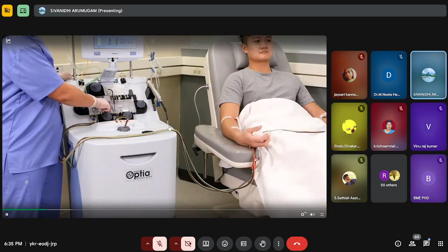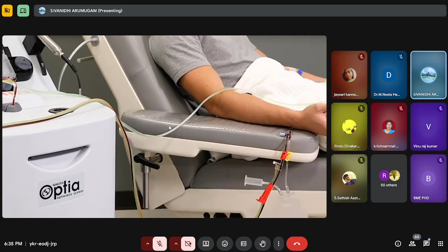And this tube, we have two tubes, one for inlet, one for the return. So this orange color and green color, this orange color is to take blood from the donor. So he's a donor, we are taking his blood and giving it to the tubing set. It is continuously pumped through the tubing set and back to the patient during the procedure. The system cycles through several accumulation and collection phases during the procedure. During each accumulation phase, the chamber fills.